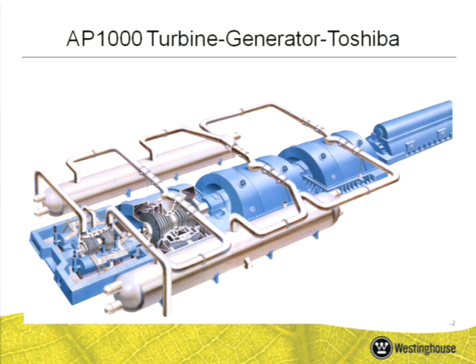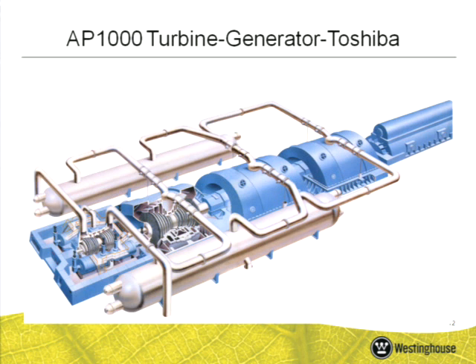This has got nothing to do with it. This is what makes the money for our customers, this is the thing that produces electricity. And basically electricity is produced by steam. The first device here is a high pressure turbine, and then there are 3 low pressure turbines, and this device separates moisture from the steam so that the low pressure turbines can work. The last device at the end is the generator, that makes electricity. That's the whole purpose of the nuclear plant, to generate electricity for the grid.